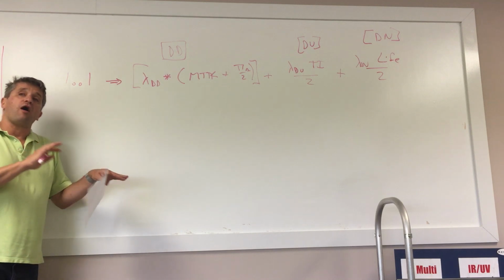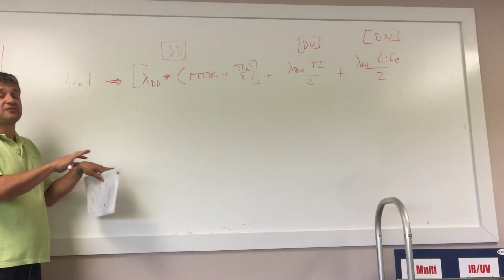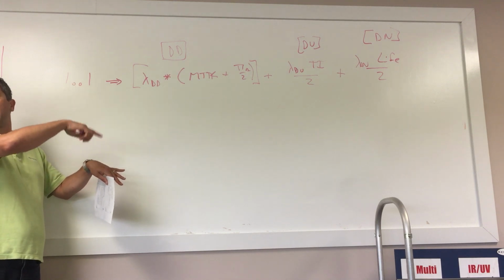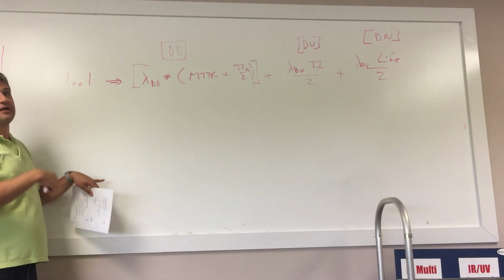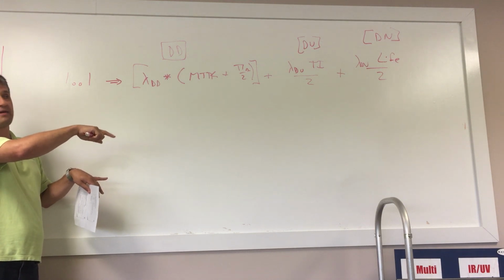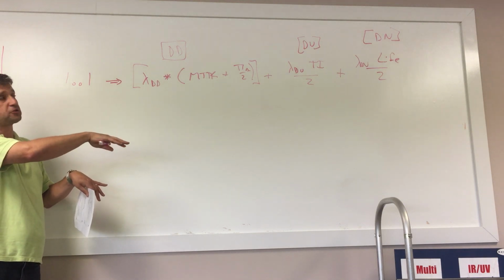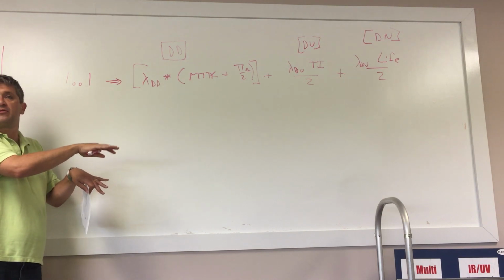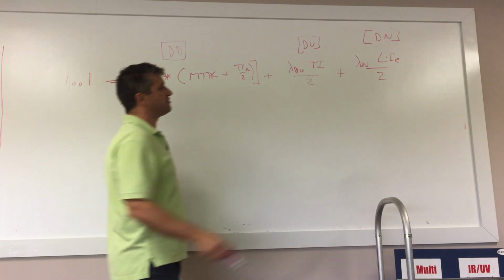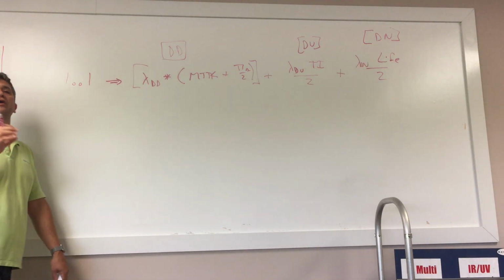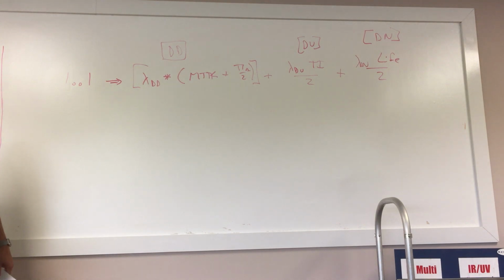Now, when you're offline and you're testing that valve under no pressure, it might move just fine. But then when you bring the process online and you try to stroke that same valve when it's under process pressure, there might not be enough force to cause it to move. So that is the type of failure that would never be detected even with manual proof testing.